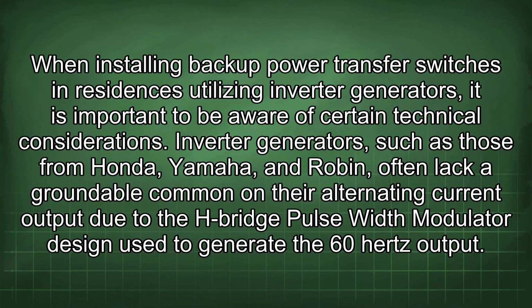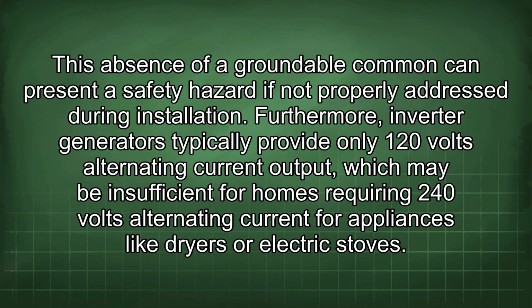When installing backup power transfer switches in residences utilizing inverter generators, it is important to be aware of certain technical considerations. Inverter generators, such as those from Honda, Yamaha, and Robin, often lack a groundable common on their alternating current output due to the H-bridge pulse width modulated design used to generate the 60 Hz output. This absence of a groundable common can present a safety hazard if not properly addressed during installation.